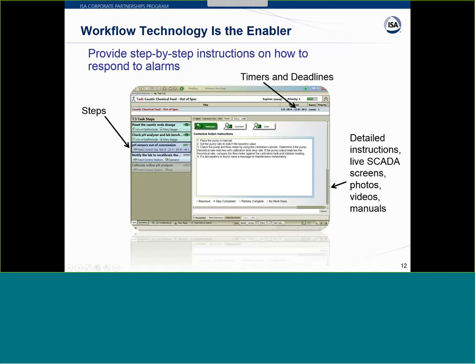What you see here with this type of system is that we had a high distillation column limit that was hit. As soon as we received that trigger, we instanced the alarm response, and immediately the first step behind the scenes sends notifications to the operations supervisor and safety personnel, and that's all automatic. The type of notifications you can send is completely varied, and with the technologies we have, it goes all over the spectrum.